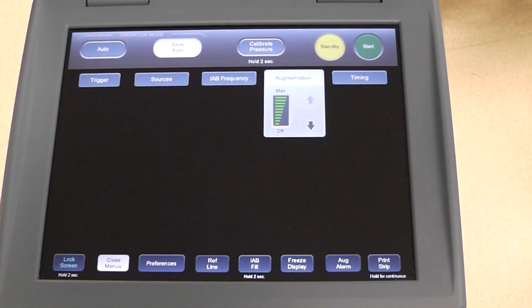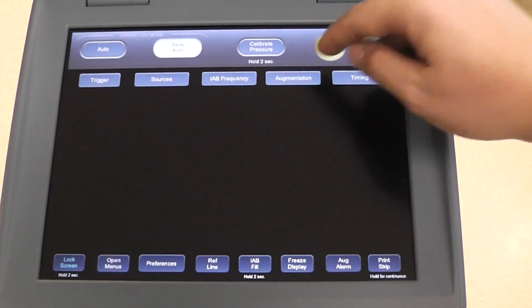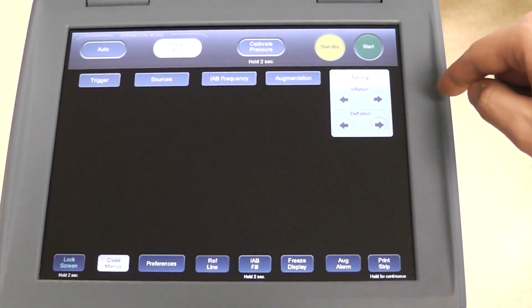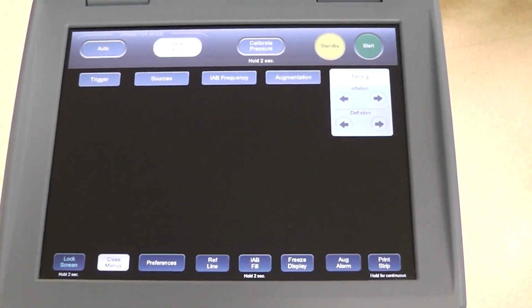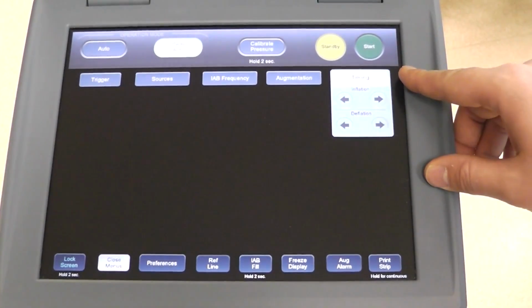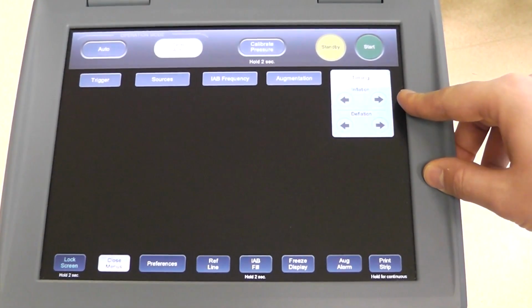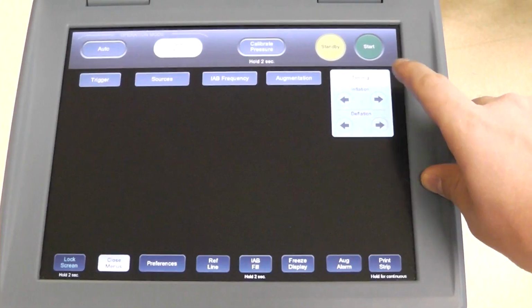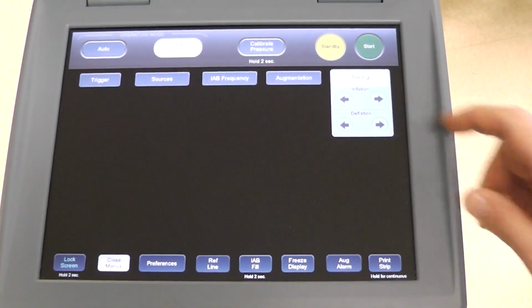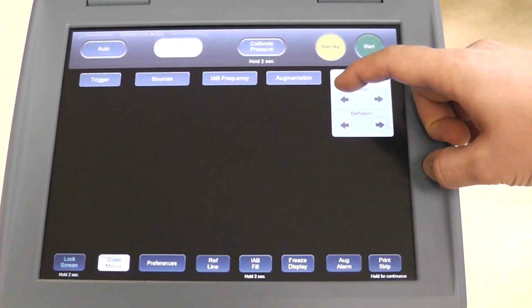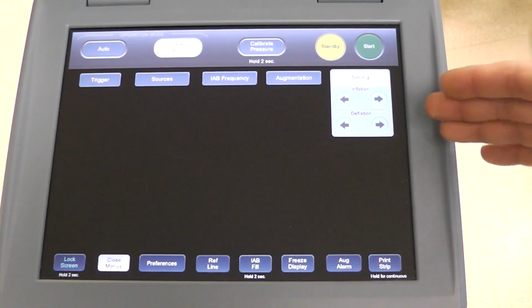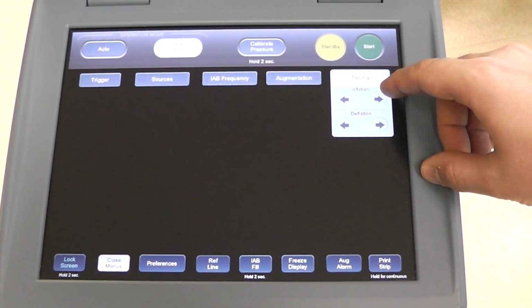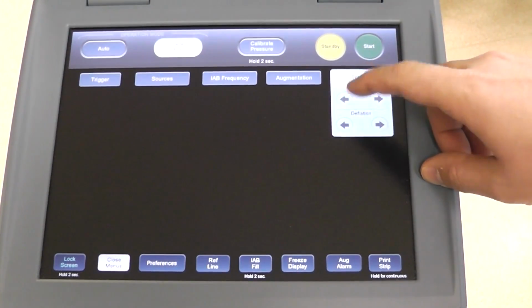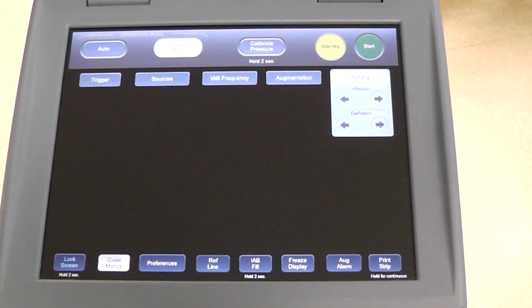Here under augmentation, we can select the amount of augmentation, or the amount of gas that's shuttled into the balloon. And here on the far right is where we are going to do most of our adjusting. Now this timing button, when you bring down the menu, you'll see inflation left and right and deflation left and right. So essentially the left would be earlier inflation, right would be later inflation, and the same for deflation.